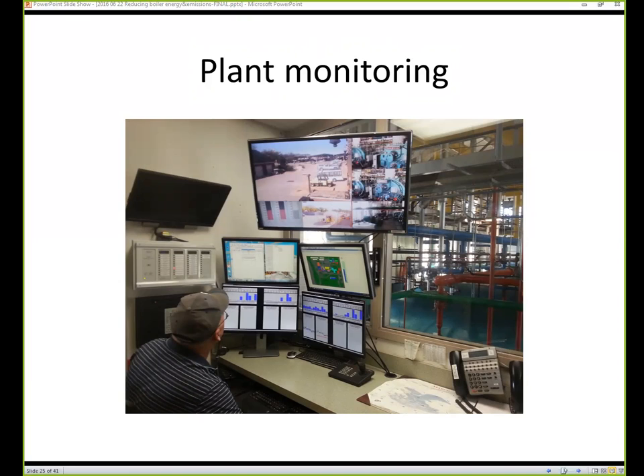The second monitor to the left is where we have a Veeder-Root underground storage tank monitoring screen where we can see and pull up all the tanks and their testing and information and print it off, send it to the state, keep it in our record. This screen is also where we have access to our data log sheet that operators fill out hourly. The second screen to the left is our building management screen to access and control all heating and air conditioning throughout the facility. Bottom screens are for the boilers and auxiliary equipment. All this information is stored and can be looked up on the hard drive. To your far left is medical gas alarm and fire alarms, which you monitor and control. I believe this setup is invaluable to the safety and efficiency of our facility.